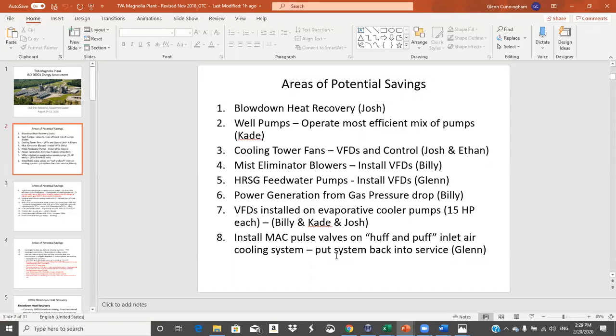Well, after a short period of operation, these diaphragm valves, these pulse valves, have diaphragms in them, and those diaphragms tend to rip. And when the diaphragms rip, they just leak compressed air like crazy. So you've got a 3 inch pipe or something feeding compressed air to a diaphragm valve that's just blowing air. And that's taking more away from the compressor, because that's coming out of the compressor that's going to your gas turbine. So that's killing you, okay? So TVA just decides, we're just going to scrap this. So they weren't cleaning them. They would go once a year, come down, and then go in and manually clean these filters.